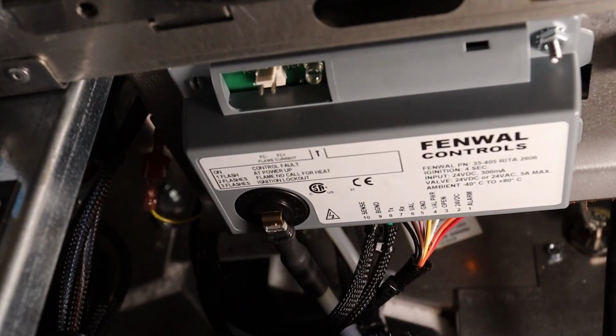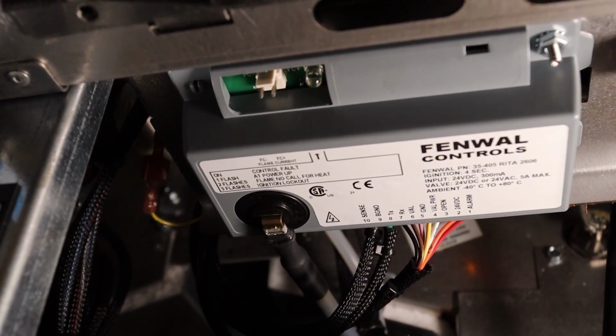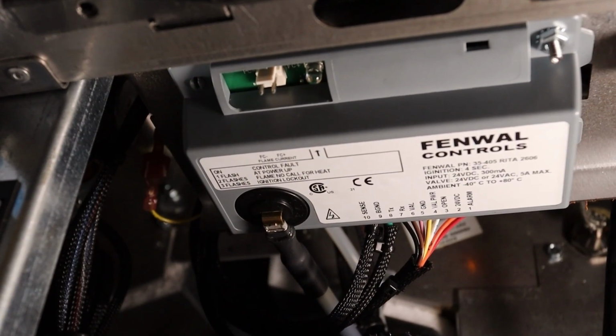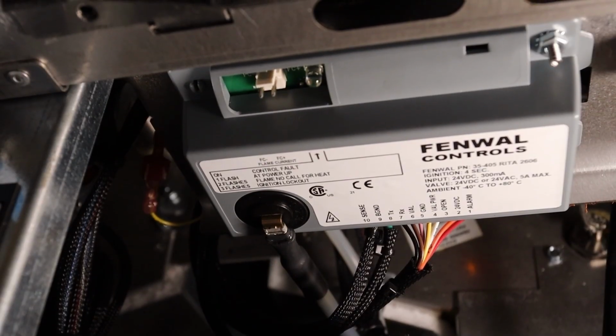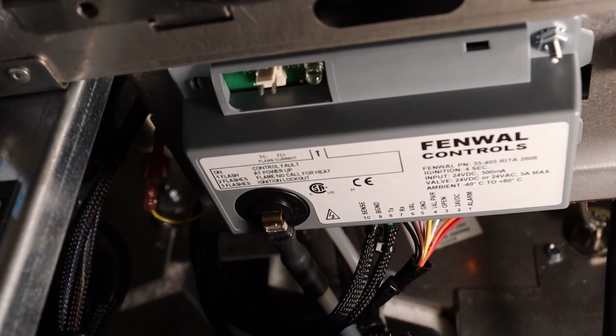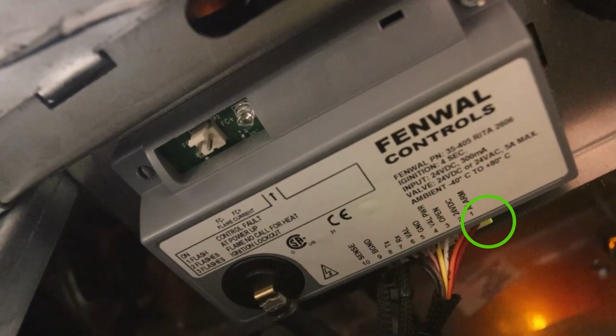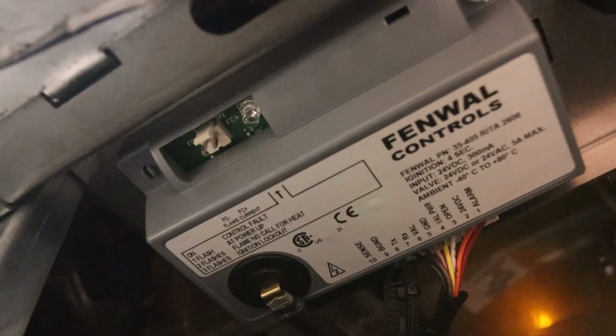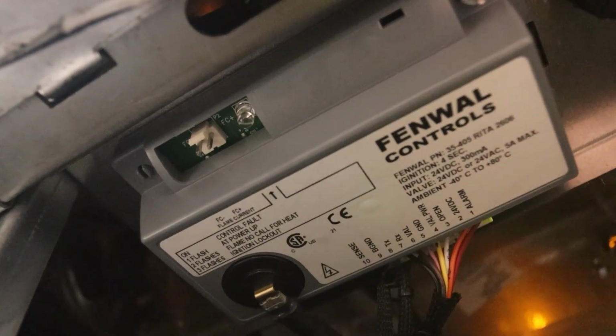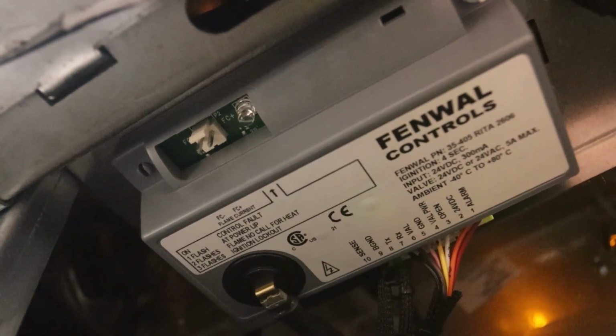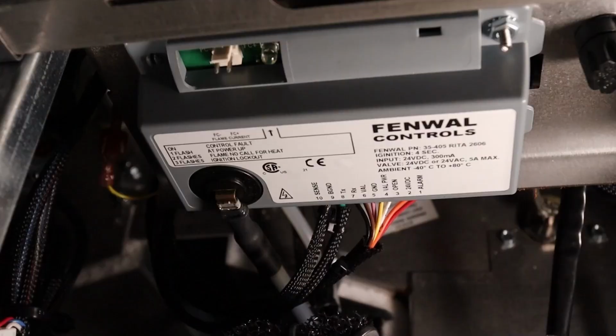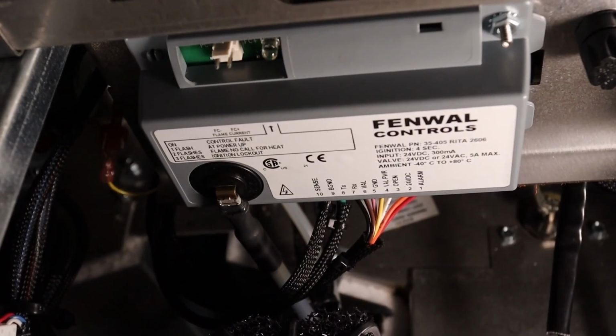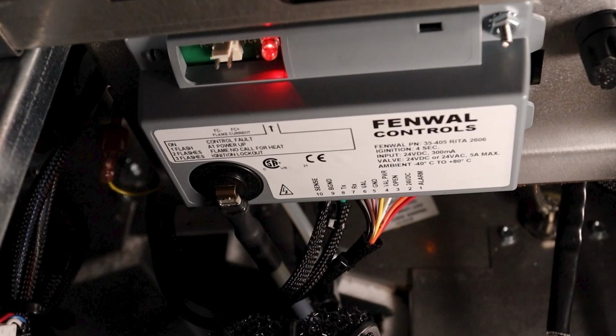3 flashes means flame was not sensed after an attempt at ignition. The module will try 4 more times, once every 5 seconds. It locks out if it doesn't sense flame. The green LED means 24 volts DC is on the module from the power supply. The LED is lit for the duration of the call for heat. If the power available to the module is less than 18 volts DC, the red LED illuminates solid.